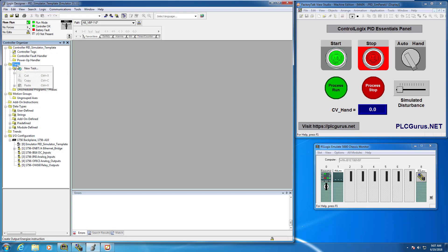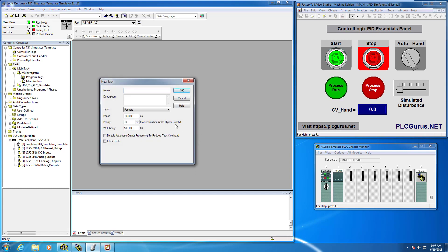Let's right-click on the task, select create new task, and we're going to call it 'loop control'. I'll leave all the other defaults as they are. When we add our PID Enhanced Instruction to our routine, it will automatically get a delta T of 10 milliseconds.